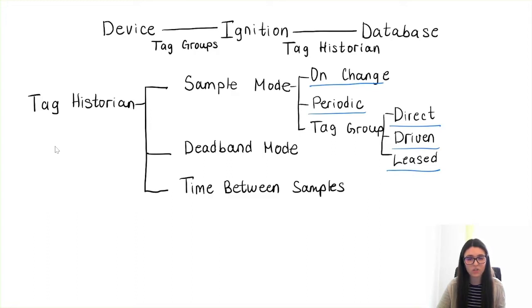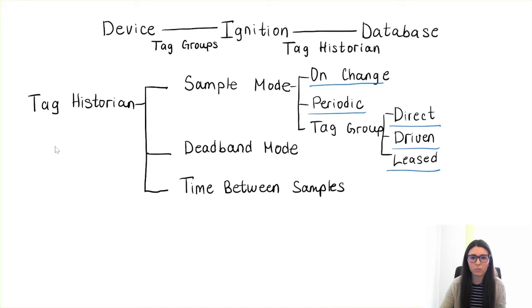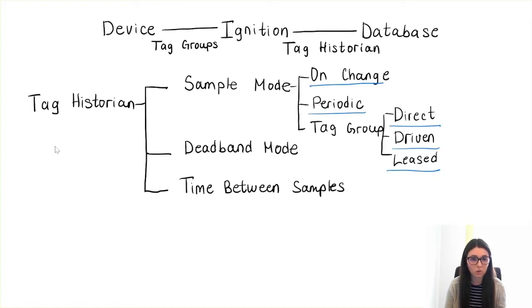The on change mode is in most scenarios the most preferred and most used one, because we are storing values into the database only when the tag value has changed. That gives us the raw data in the database — nothing more — which gives us the flexibility to perform analysis, aggregation, fill holes, and so on.